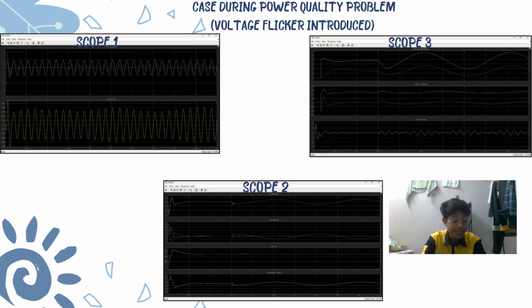Scope 2 displays the internal controller signals, which are the reactive current Iq tracking its reference Iq ref, and also the reactive power, which is Q. It swings sinusoidally, with active power remaining low and the DC link voltage staying stable at 3000 volts. The modulation index adjusts smoothly, ensuring that the inverter responds passively to load changes.